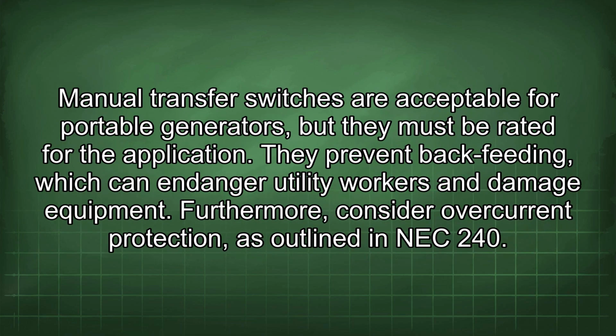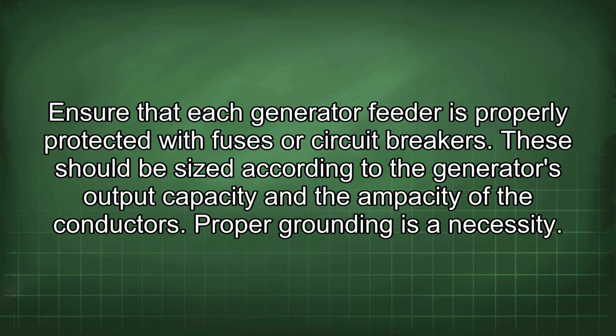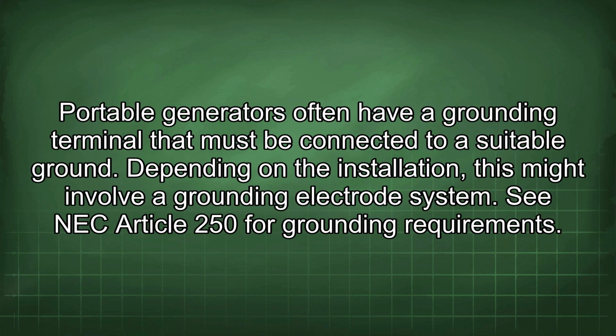Fourthly, transfer switches are essential for safely switching between the utility power and the generator power. Manual transfer switches are acceptable for portable generators, but they must be rated for the application. They prevent backfeeding, which can endanger utility workers and damage equipment. Furthermore, consider overcurrent protection as outlined in NEC 240. Ensure that each generator feeder is properly protected with fuses or circuit breakers. These should be sized according to the generator's output capacity and the ampacity of the conductors. Proper grounding is a necessity. Portable generators often have a grounding terminal that must be connected to a suitable ground. Depending on the installation, this might involve a grounding electrode system. See NEC Article 250 for grounding requirements.